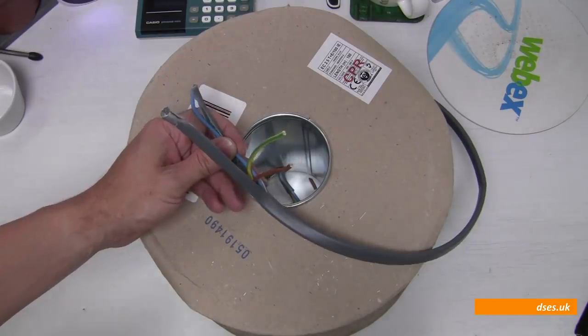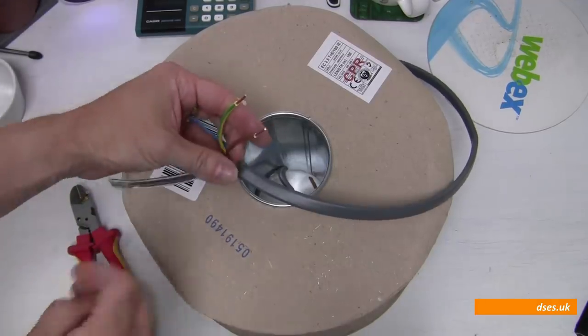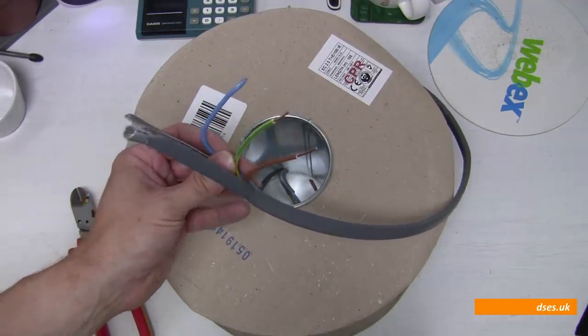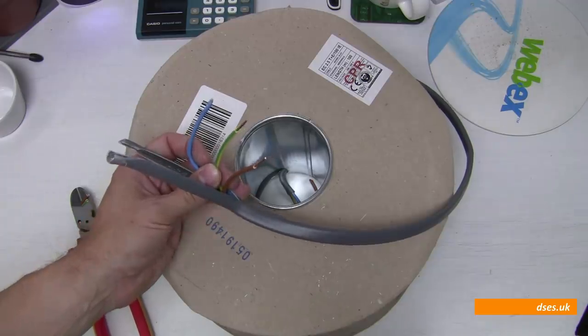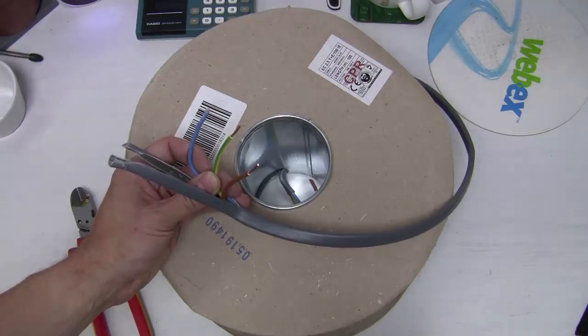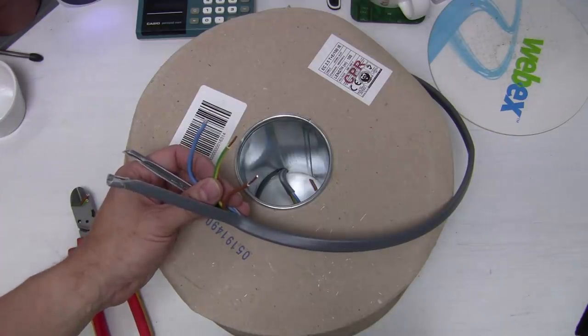But hang on — a sleeved protective conductor surely can't be adding an extra three kilos to the thing. Well, no. There's one other thing to note here about the CPC, and that is that it's the same cross-sectional area as the line and neutral conductor. So this is a 3 core 2.5 — it's not a 2.5/1.5, which is what you'd get with its UK counterpart. It seems that in 2013 the wiring regulations in the Republic of Ireland were changed to require the size of the CPC to match that of the line conductors. Over here, twin and earth cable is still made with a smaller diameter earth conductor to save copper, save cost, make for a more malleable cable, and because we assume all circuits are correctly designed so that automatic disconnection of supply will occur in the event of a fault, and before a big enough and sustained enough current can heat that smaller CPC core sufficiently enough to cause trouble. Maybe the lack of sleeving aids in heat dissipation, and maybe the Irish requirement to sleeve the CPC is what has driven up its size. I genuinely don't know, and I'm far too lazy to start Googling for answers now, so I'll rely on those more clued in to comment below.